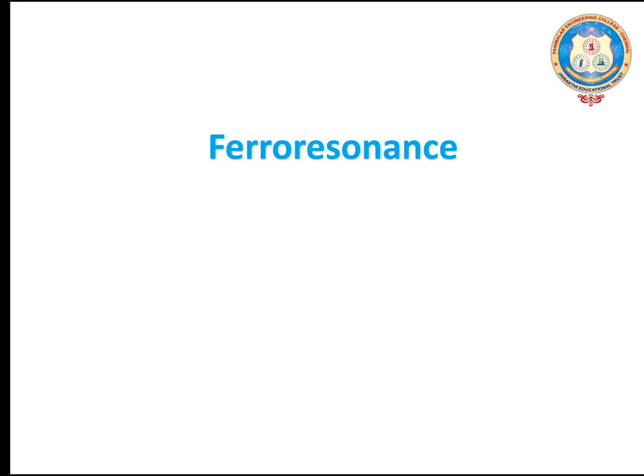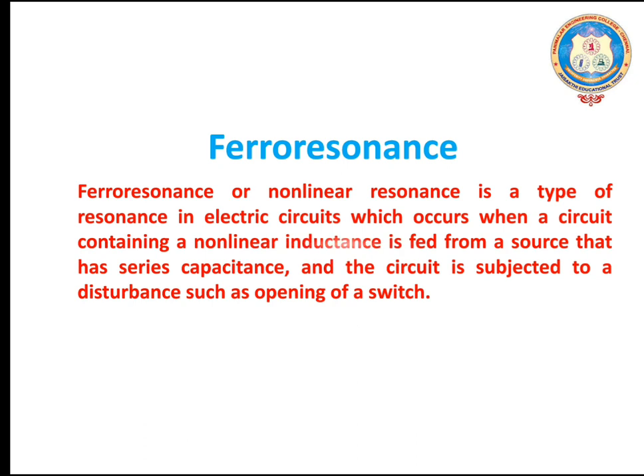Define ferro-resonance. Ferro-resonance or non-linear resonance is a type of resonance in electric circuits, which occurs when a circuit containing a non-linear inductance is fed from a source that has series capacitance and the circuit is subjected to a disturbance such as opening of a switch.